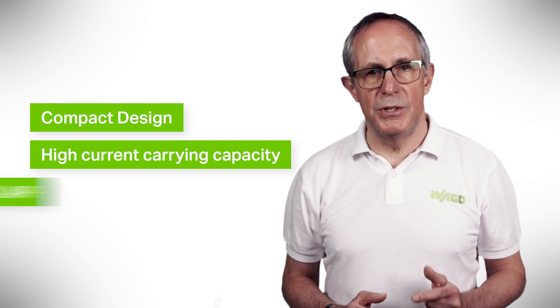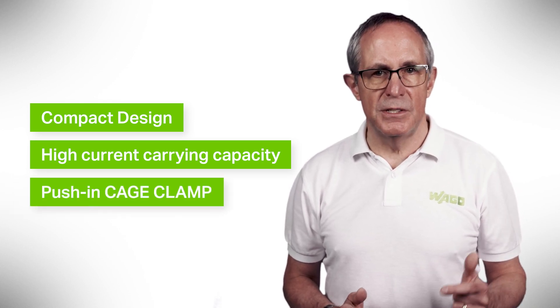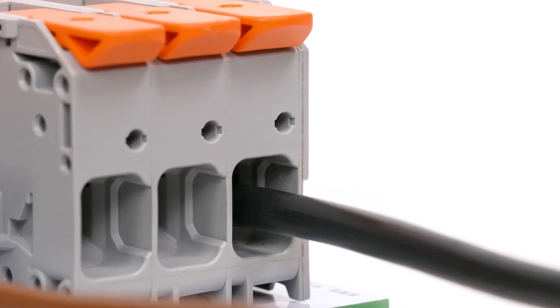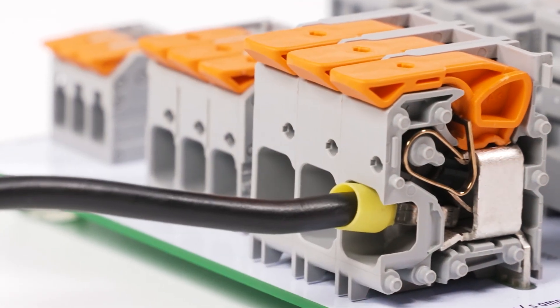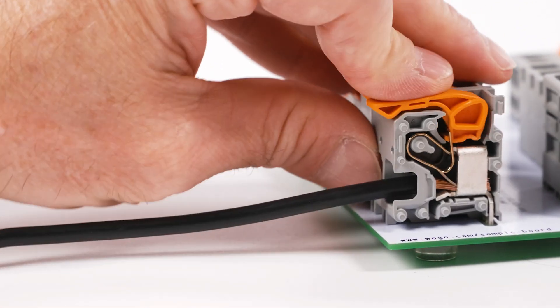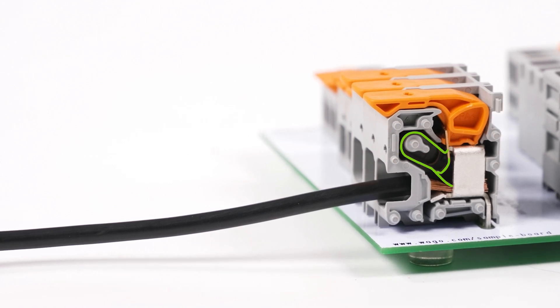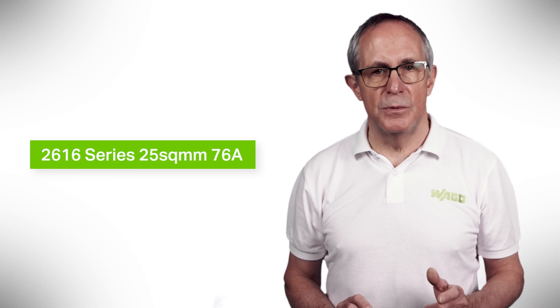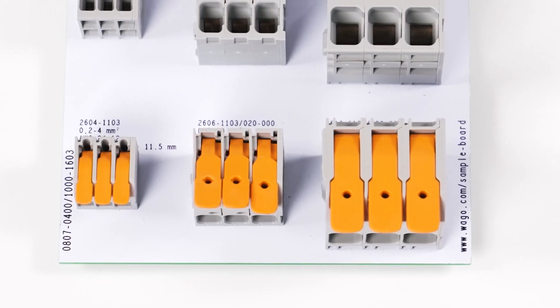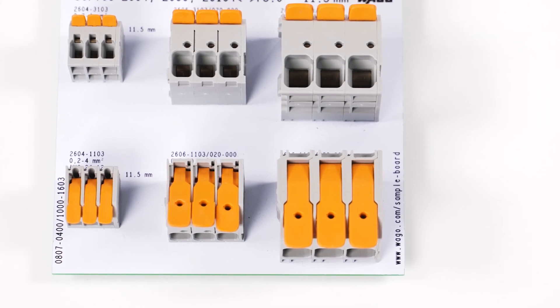WAGO's lever-operated PCB terminal blocks offer faster and easier wiring. They combine a compact design, high current carrying capacity, and the advantages of push-in cage clamp for solid and ferrule conductors with the benefits of intuitive lever technology. The lever provides 100% tool-free operation and a secure connection every time. It engages to keep the clamping point open, freeing both hands for quick and easy wiring, allowing all conductor types to be connected and disconnected without tools. The terminals range from the 2616 series at 25 square millimeter and 76 amps down to the new 1.5 square millimeter, 17.5 amp 2601 series version, bringing lever connection to signal conductors. Importantly, they look the same and operate in the same way in all sizes, so connection is clear and simple whatever the application.